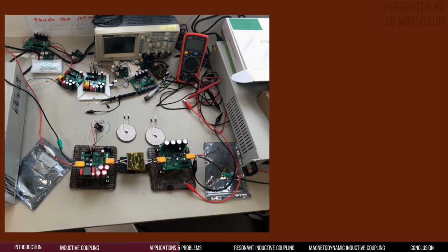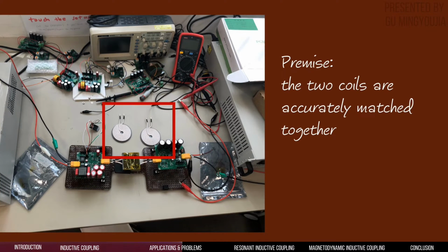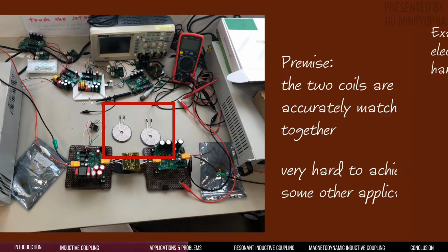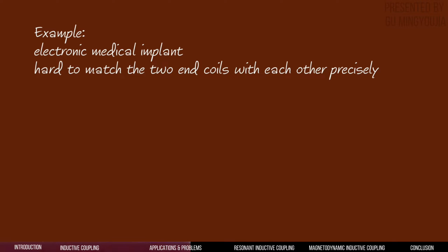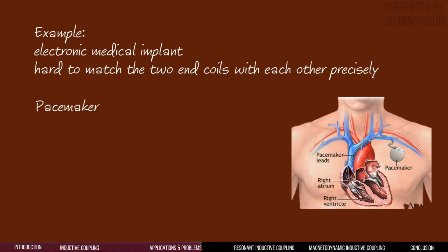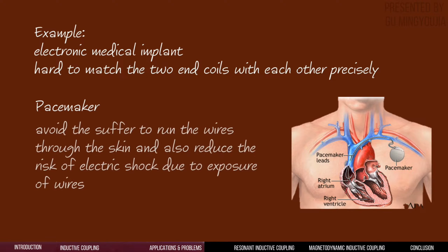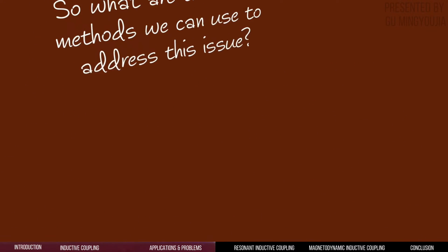However, this is under the premise that the two coils are accurately matched together, which is very hard to achieve for some other applications. One of these applications is electronic medical implants, where it is definitely hard to match the two end coils with each other precisely. However, wireless charging for medical implants like pacemakers has significant meaning, as it can avoid the need to run wires through the skin and reduce the risk of electrical shock due to exposed wires.